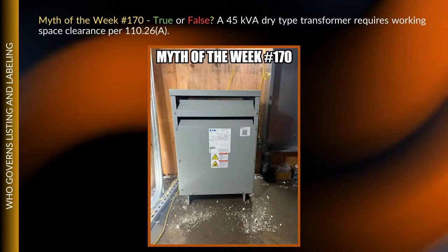Without reading anything else in the code, I think we'd all agree you cannot get to that working space safely, and once there, you cannot maintain or operate that equipment safely. Forget 3 feet, 30 inches, 6.5 feet, all of that. The first thing you have to figure out is: can I even operate this equipment safely? If you can't, you don't have to read anything else in the code—you know it doesn't comply. You need to be able to get to it safely, leave it safely, and operate and maintain it safely.